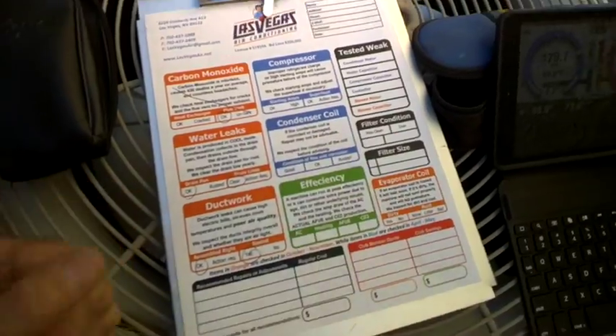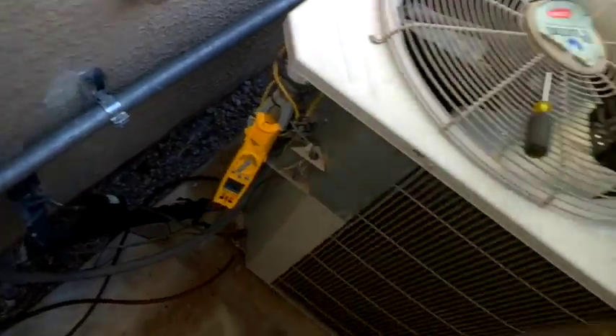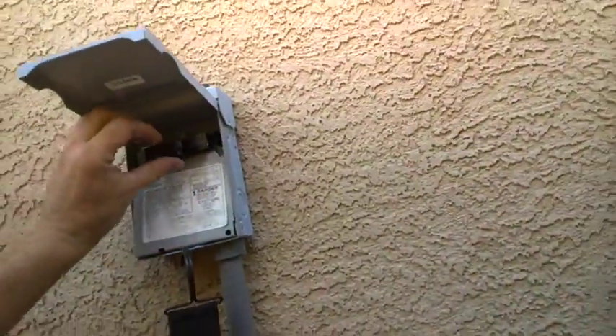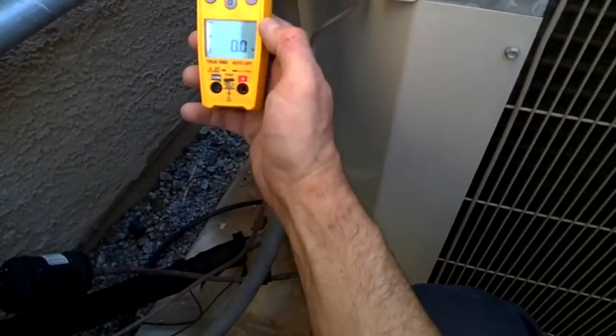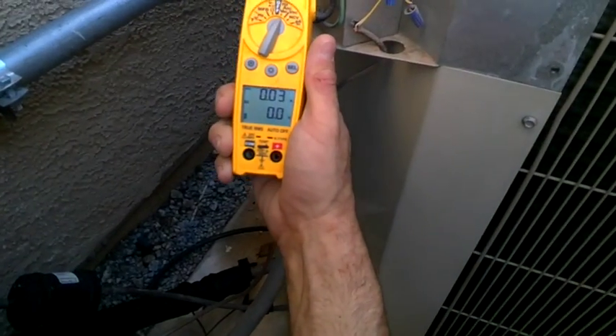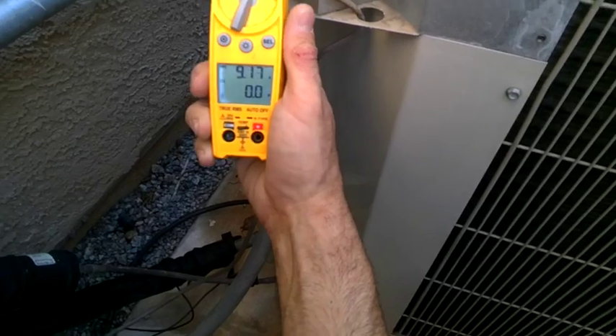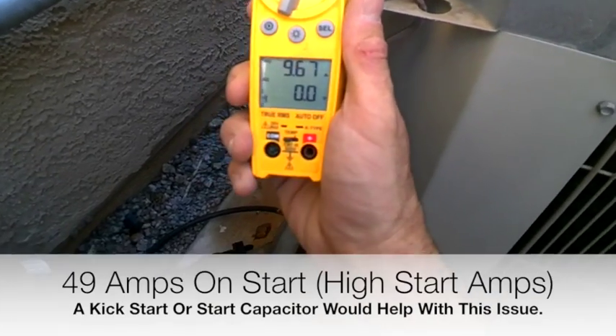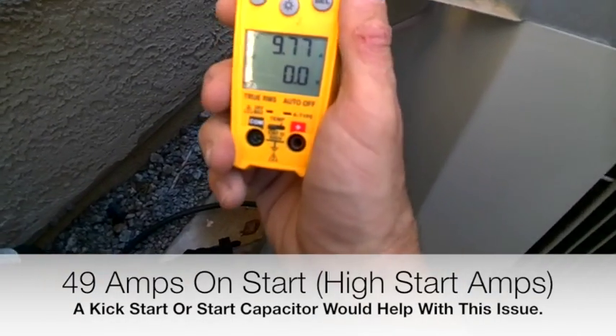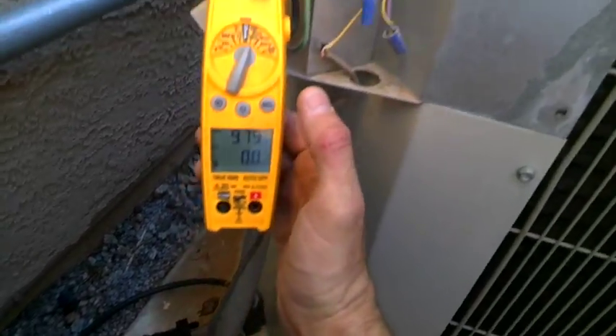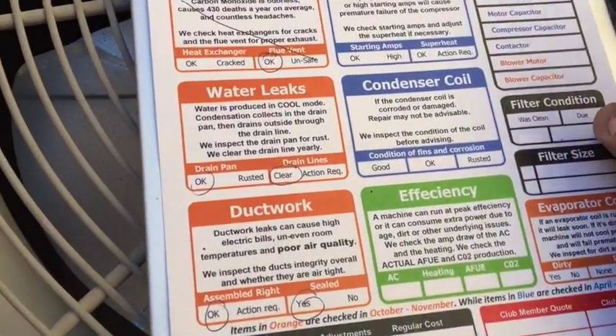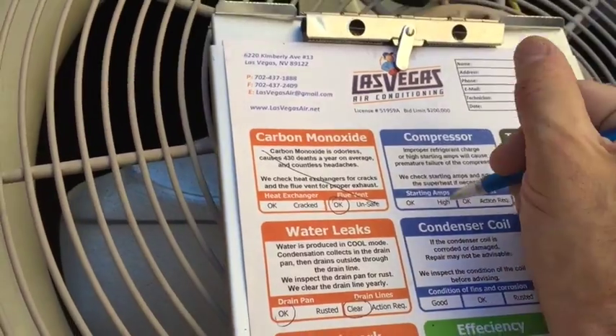Now we're going to check its starting amps. So the way we're going to do that is we had to have everything off for a while. And we're going to get ready to give it power. Watch our amp probe here. 49 on start, so a slight high starting amp on this compressor. Okay, so the starting amps were a little high.